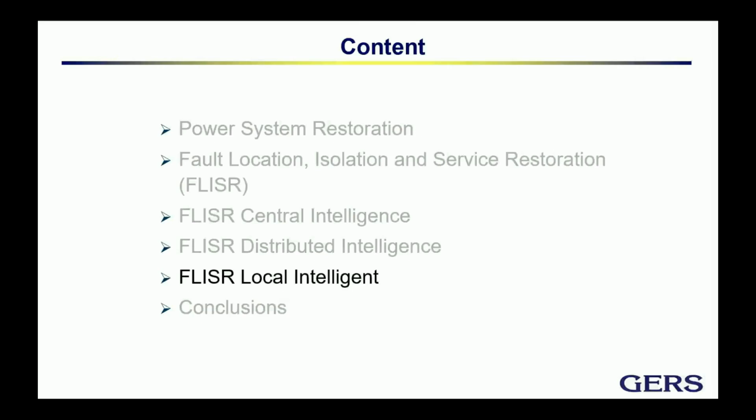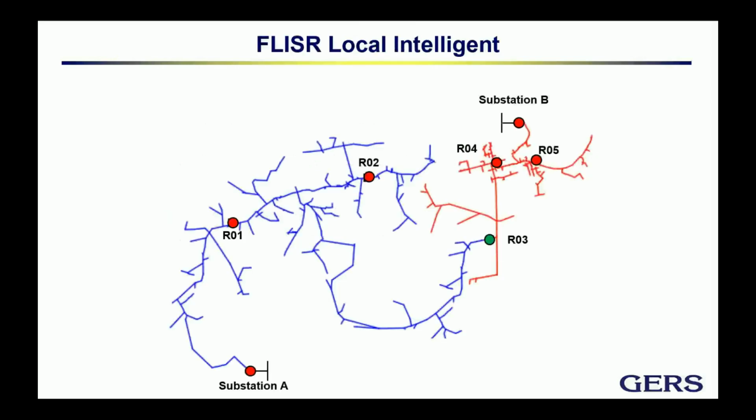I was saying that the old technology where reclosers were used in conjunction with sectionalizers still exists. In those days, we basically didn't have any communication. Basically, we had these reclosers that would have, of course, relays, and they were working with sectionalizers that were counting the number of reclosing operations to do a proper operation. Still that exists, and in many rural areas that is very much used. We can't, let's say, neglect that.